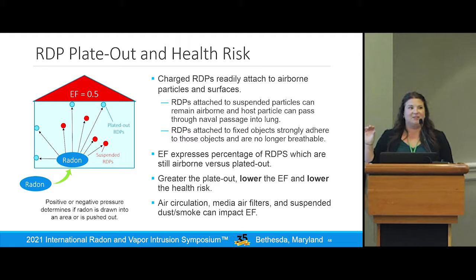I also want to note that positive or negative pressure determines how much radon actually enters the building. If the building is under positive pressure, it helps keep radon gas out. However, if it's under negative pressure, because of imbalanced HVAC or something similar, it will really draw that radon gas into the building.